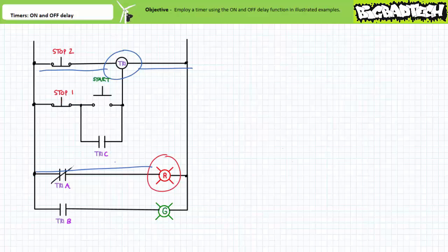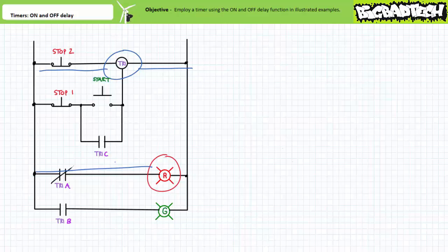If you think about it, the function of both the start and Stop 1 buttons in this circuit is to allow the operator a full five seconds to contemplate if starting up or shutting down this system is really what they mean to do. Such a ladder logic diagram could be used to ensure that the startup and shutdown of some expensive or mission-critical system isn't just a passing fancy, but rather an intentional action you're at least willing to wait five seconds for. Stop 2 would serve to completely depower the timer relay for the purposes of overriding whatever time function is occurring at that moment and returning the system to the de-energized start state — red light on, green light off.